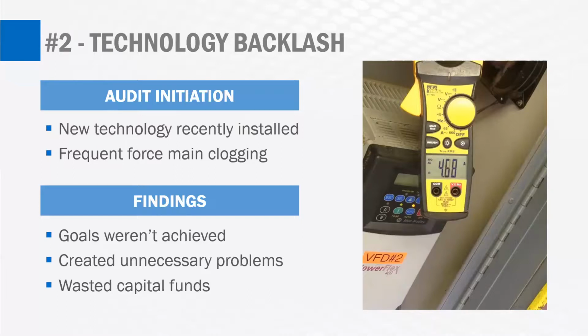The initial intent was to have the VFDs speed up the pumping rate at least once or twice per day to achieve scouring velocity. It turns out that was not occurring, and that led to solids deposition in the force mains, and then eventually the clogging issue. So overall, the audit was able to reveal that the goals of the electrical savings were not achieved because of this force main clogging and lost electrical efficiency due to it. It created unnecessary problems because now that force main clogging issue had to be addressed.